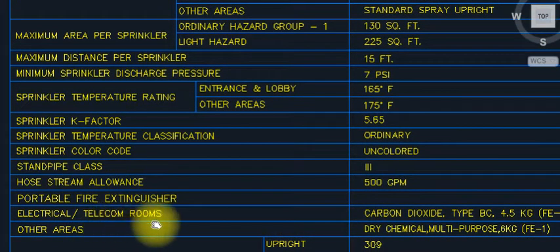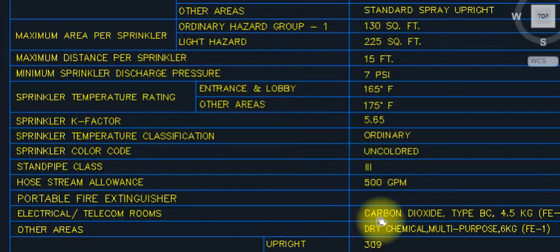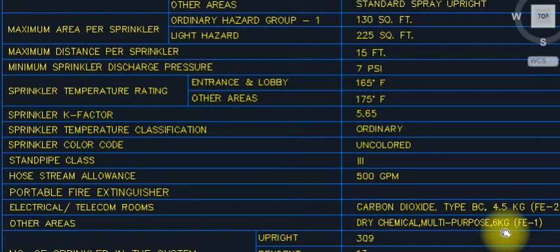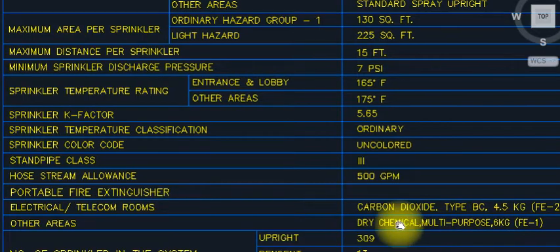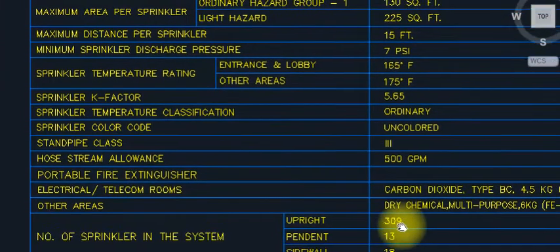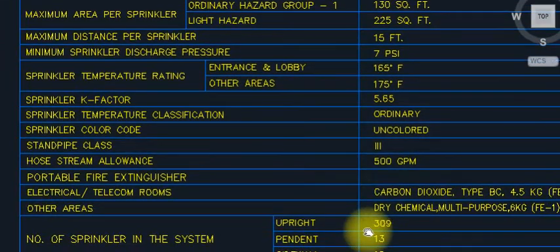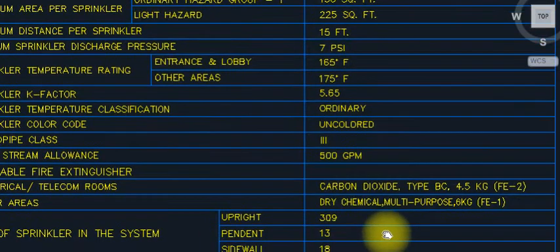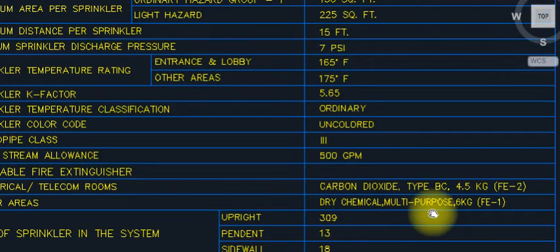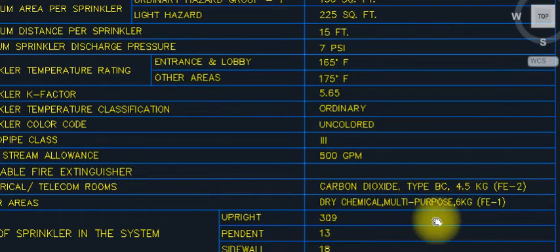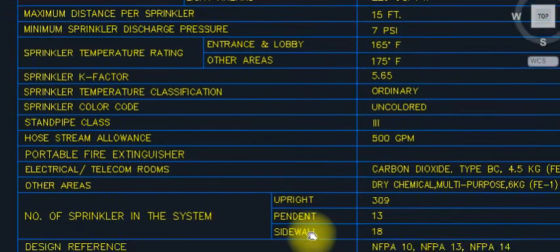For electrical and telecom rooms, we have carbon dioxide type — but now we are using FM200 system and Novec system as well. For other areas, we use dry chemical multipurpose extinguishers.